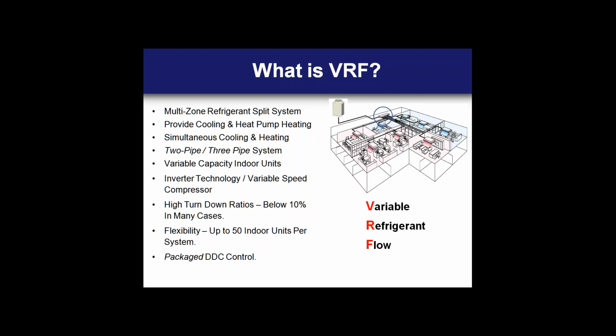So in simple terms, when we say VRF, we're talking about a multi-zone split DX system, multiple indoor units connected via a common refrigeration network to a single VRF outdoor condensing unit. That condensing unit may consist of multiple modules that are twinned together, but they all share a common refrigeration network.